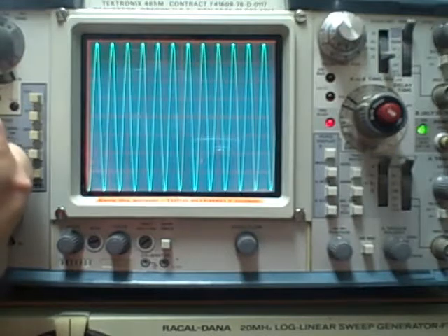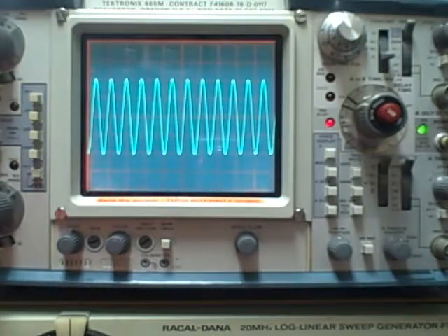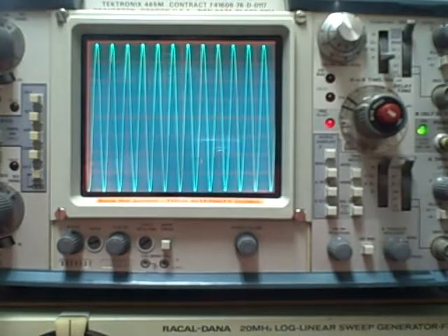Let's go ahead and drop ourselves to half scale by raising our range up to 2 volts per division. Okay, we're on the 2 volt per division scale. That means we have 8 volts going up or down, and that would require 5.656854 volts RMS out of the Fluke. So I've got that dialed in, and we're reading full scale right now, not a problem.